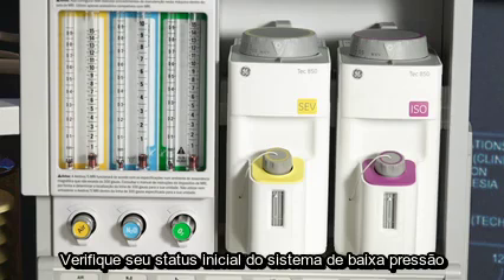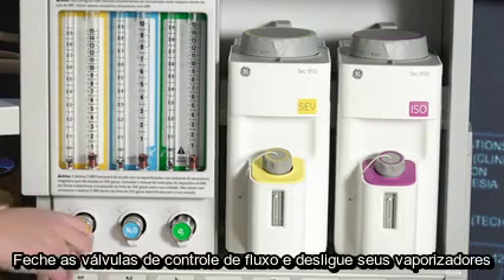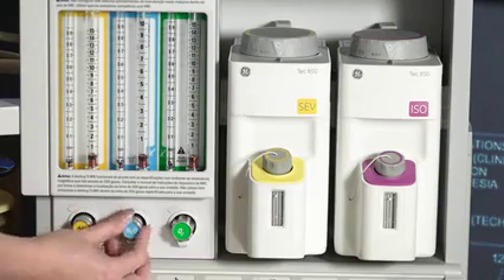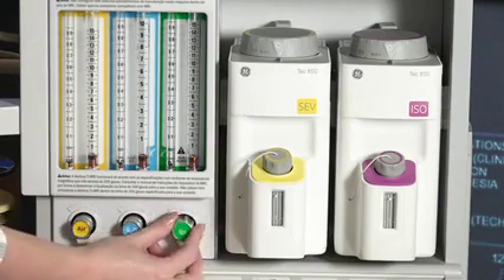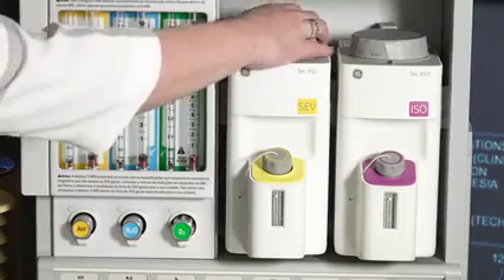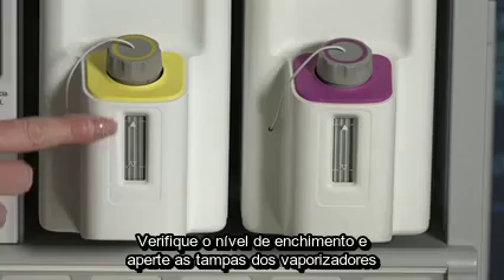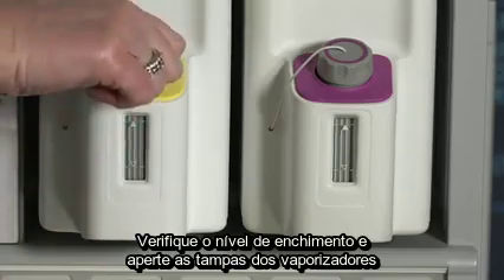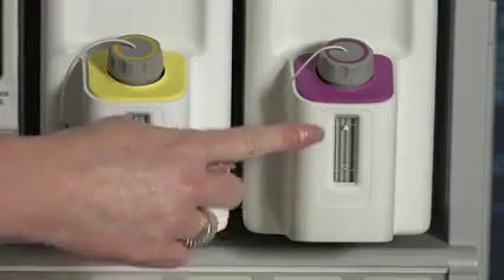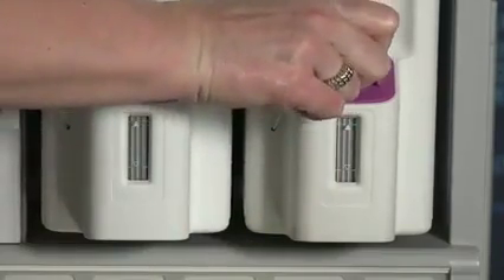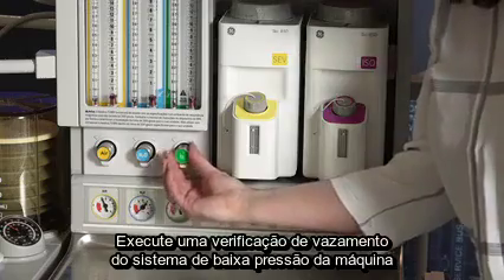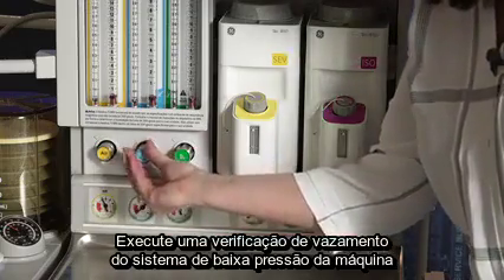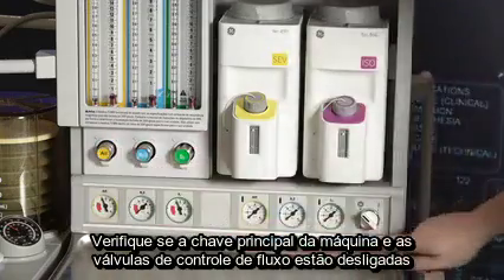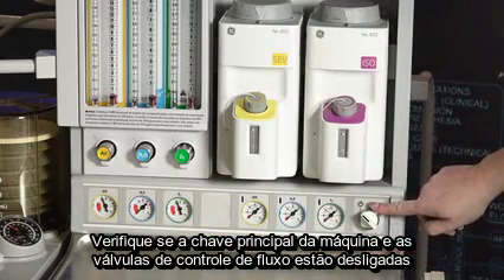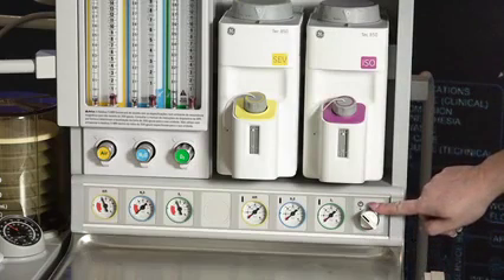Check your initial status of the low pressure system. Close flow control valves and turn your vaporizers off. Check the fill level and tighten vaporizers filler caps. Perform a leak check of the machine's low pressure system. Verify that the machine master switch and flow control valves are off.